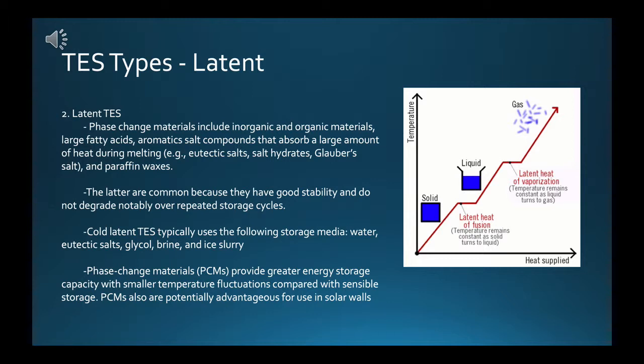Paraffin waxes are common because they have good stability and do not degrade notably over repeated storage cycles. The phase change material in latent TES can be contained in a single large vessel or in small modules such as rods or plastic containers, providing great flexibility. Latent heat TES can be used to store hot or cold. Cold latent TES typically uses water, eutectic salts, glycol, brine, and ice slurry. In solar combination systems, large solar fractions normally require larger water volumes, but PCMs offer more compact alternatives and can be advantageous for seasonal storage.